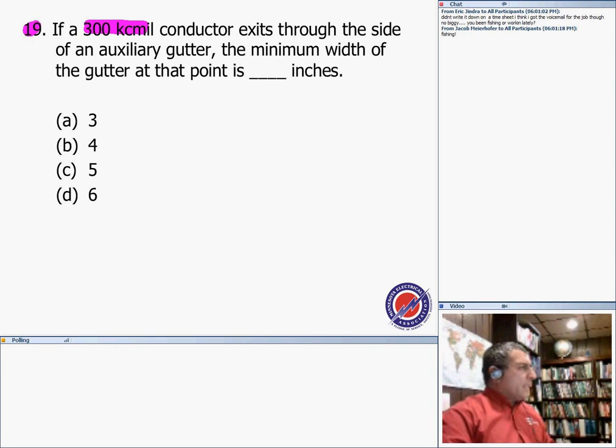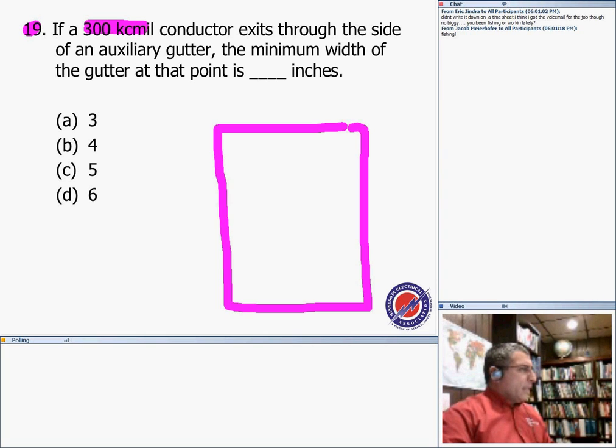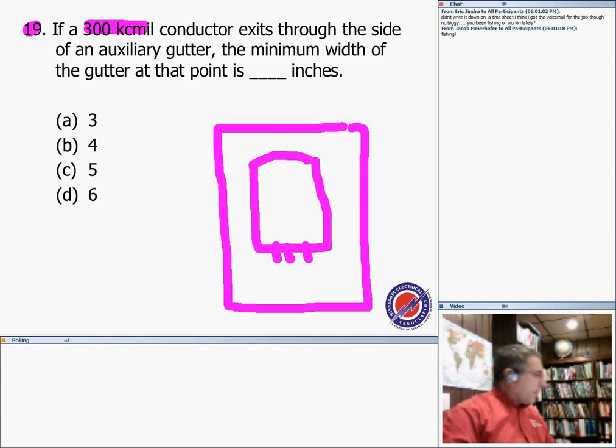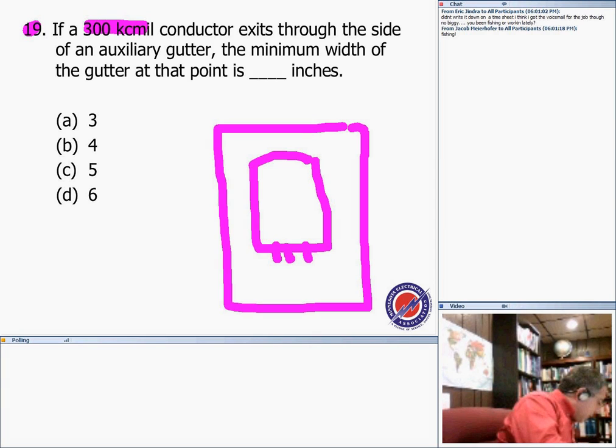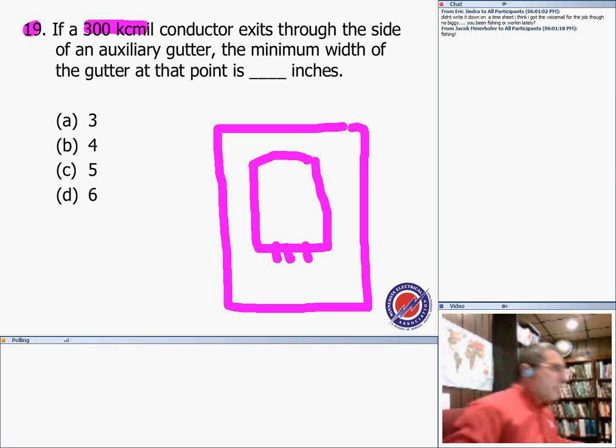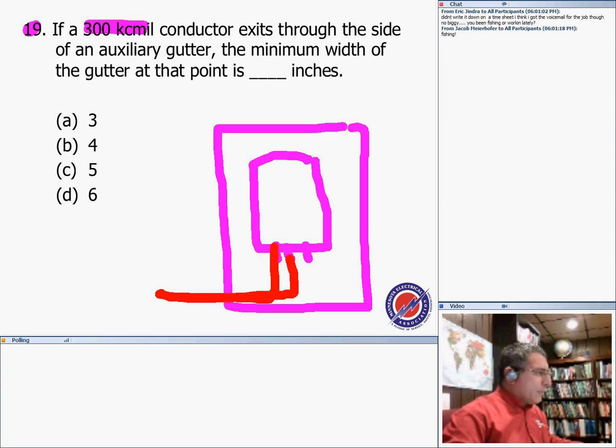If my conductor is a 300 kcmil conductor going through the side of an auxiliary gutter, the minimum width of the gutter at that point is, and we have to work it out. Say there was a terminal here, and here are my conductors. If conductors are entering and leaving opposite walls, this will be the table for conductors at terminals. This one doesn't say opposite walls, so let me have a wire like this. So I'm bringing conductors, guys, and I'm moving them this way, right? Coming from the side. I can do that. What's wrong with that? Then the width of the gutter that I'm using is going to come from the table.